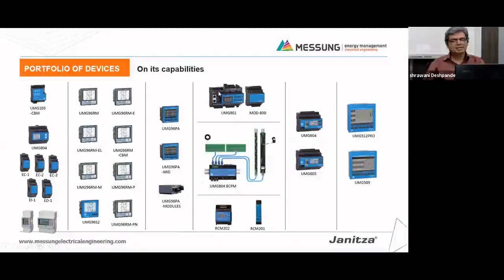Then these meters, where I am showing the cursor, are specifically for the data center. These two meters, UMG 801 and UMG 804, are for branch circuit monitoring, where you give a supply of one single voltage and you can connect different current channels, 96 current channels, using these meters. Below you can see the residual current monitoring meters, which we have designed specifically for residual current monitoring.